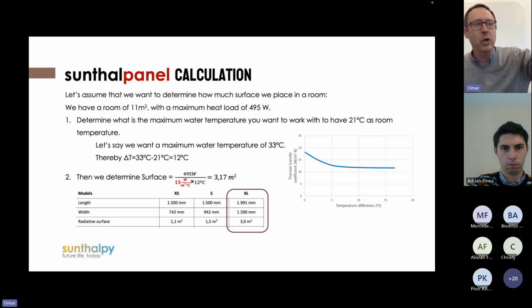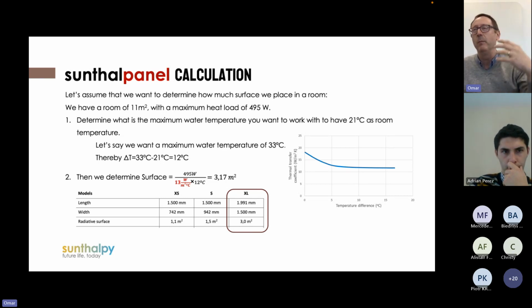But even though the floor has been cooled down, if the sun strikes, you cannot stop that. What happens is the air doesn't have mass, as we said, and doesn't have a specific heat. So the air will increase temperature very rapidly until you reach a certain temperature. The radiation of our plates, as I said before, does not cool the air, because air is not affected by radiation, because it doesn't have mass. Air is affected by convection.